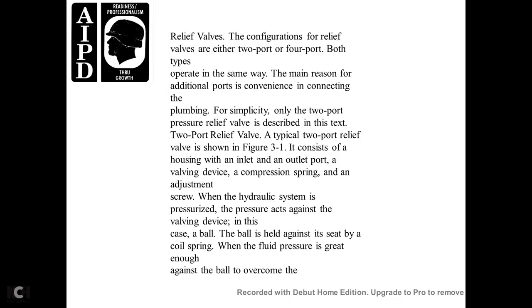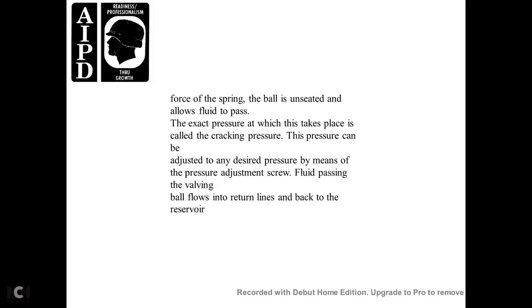Relief Valve Construction. Relief valves are configured as either two-port or four-port; both types operate the same way. Only two-port pressure relief valves are described here. The typical two-port relief valve shown in figure 3-1 consists of a housing with inlet and outlet ports, a valve device, a compressing spring, and an adjusting screw. When the hydraulic system is pressurized, the pressure acts against the valve device — in the case of a ball, it is held against the seat by a coil spring. When fluid pressure is great enough to overcome the force of the spring, the ball is unseated and fluid passes; the pressure at which this takes place is called the cracking pressure. The pressure can be adjusted using the pressure-adjusting screw. Fluid passing through the valve flows into the return line back to the reservoir.